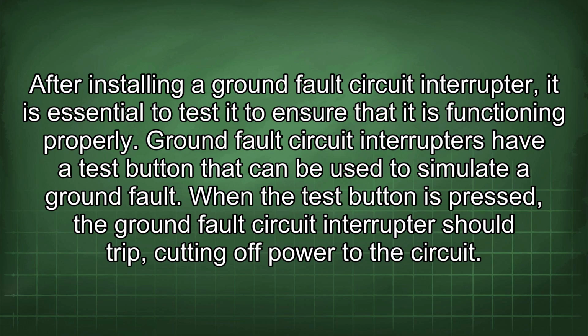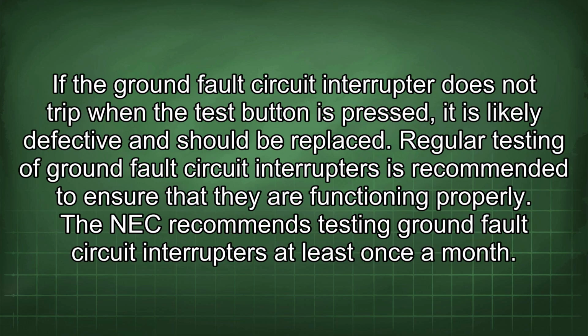After installing a ground fault circuit interrupter, it is essential to test it to ensure that it is functioning properly. Ground fault circuit interrupters have a test button that can be used to simulate a ground fault. When the test button is pressed, the ground fault circuit interrupter should trip, cutting off power to the circuit. If it does not trip when the test button is pressed, it is likely defective and should be replaced.